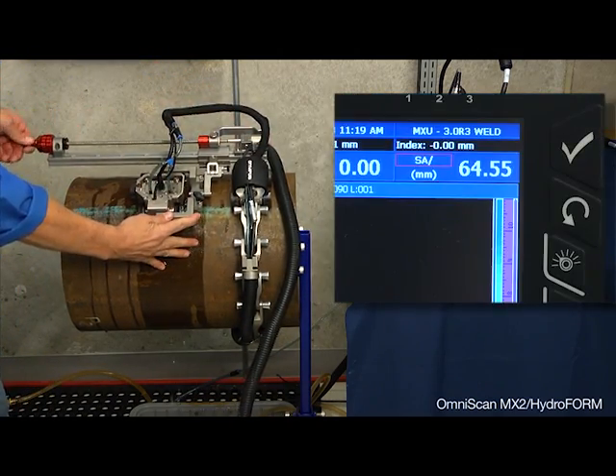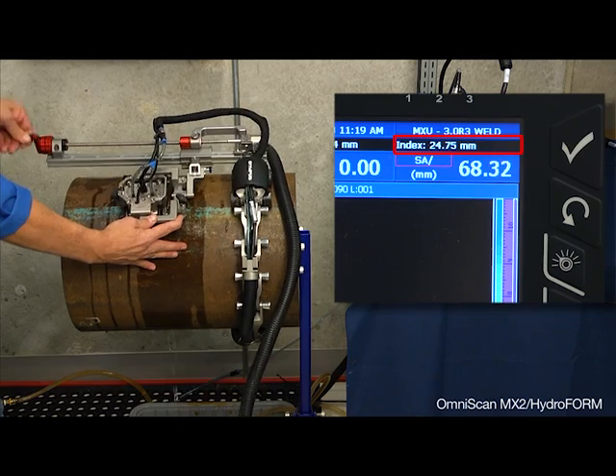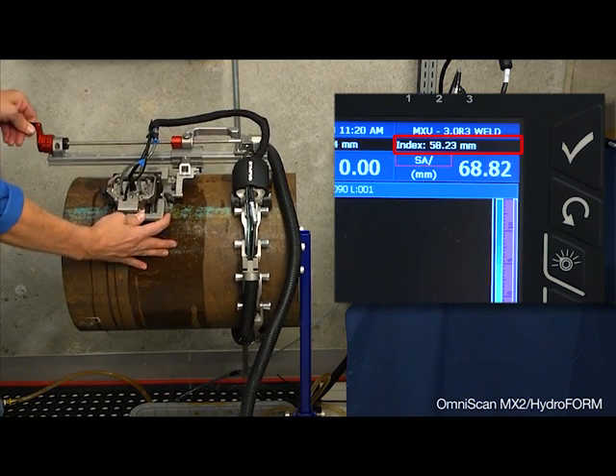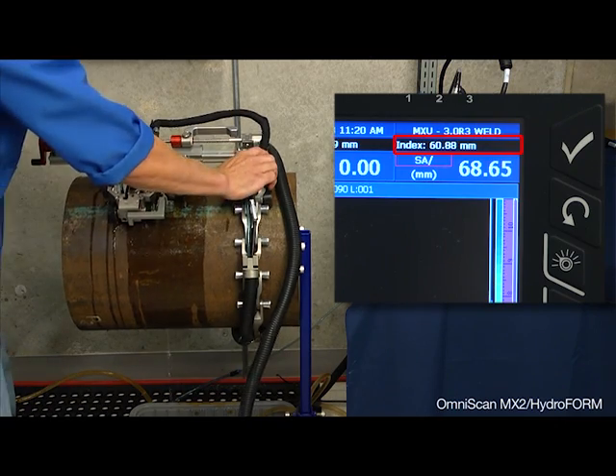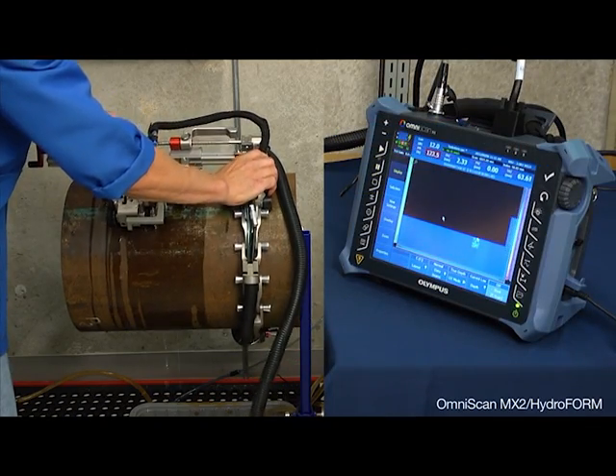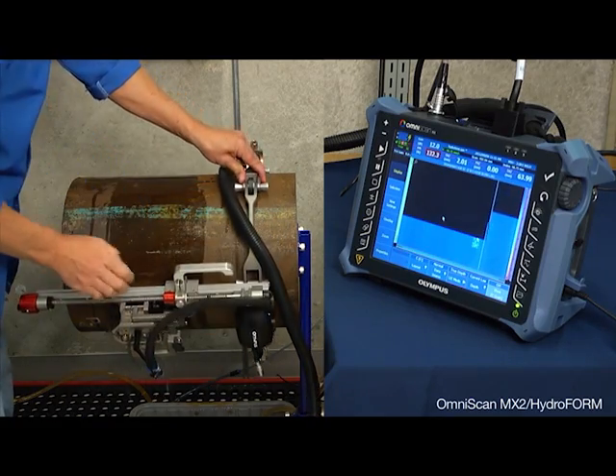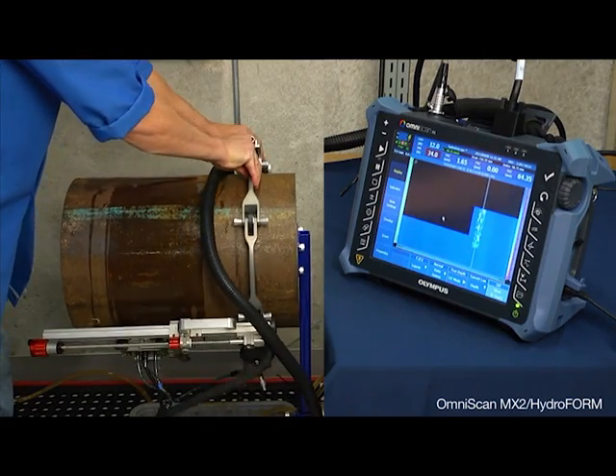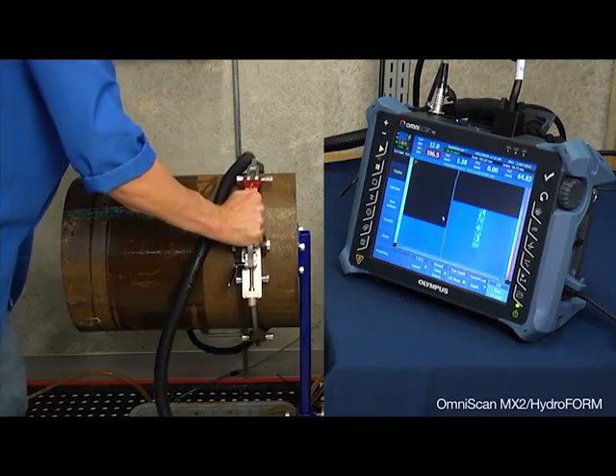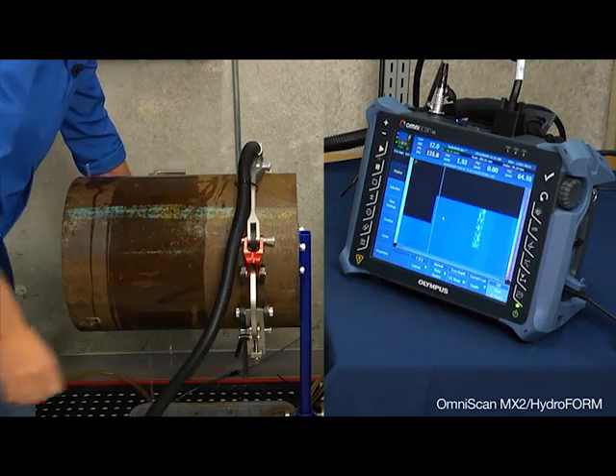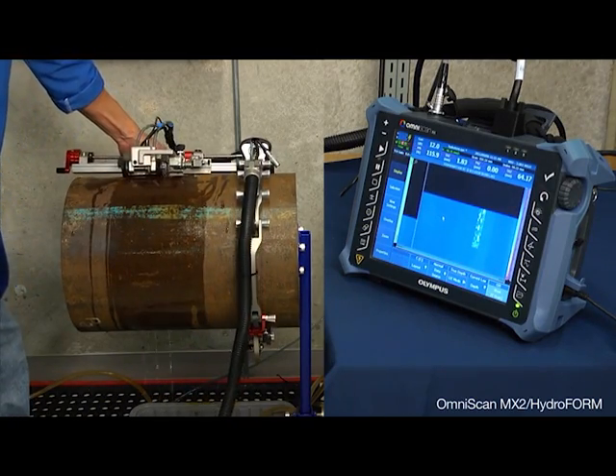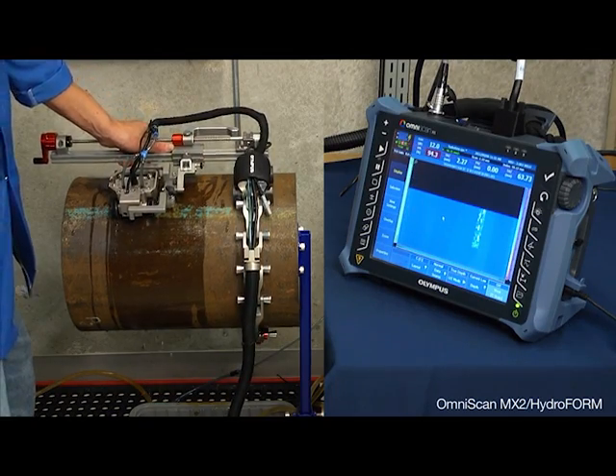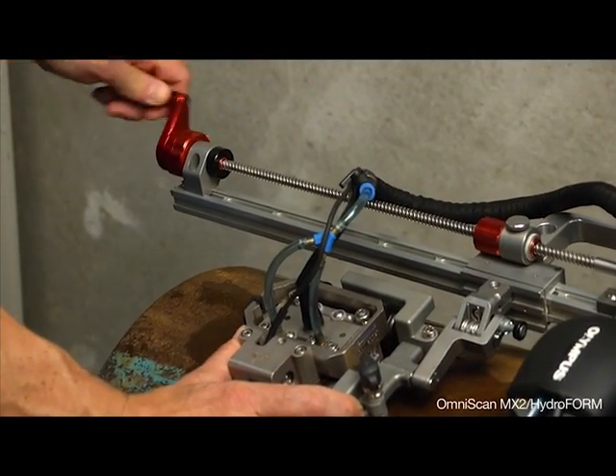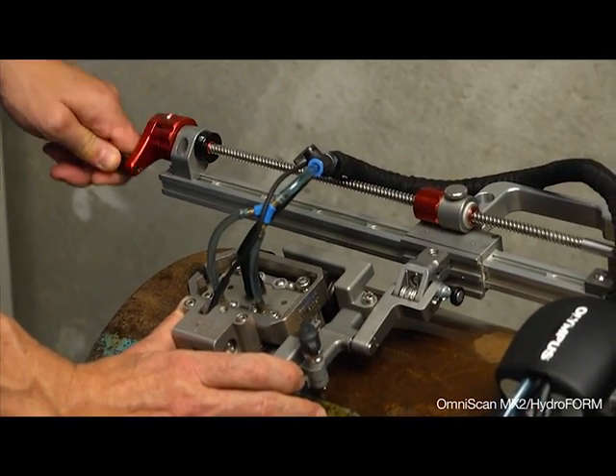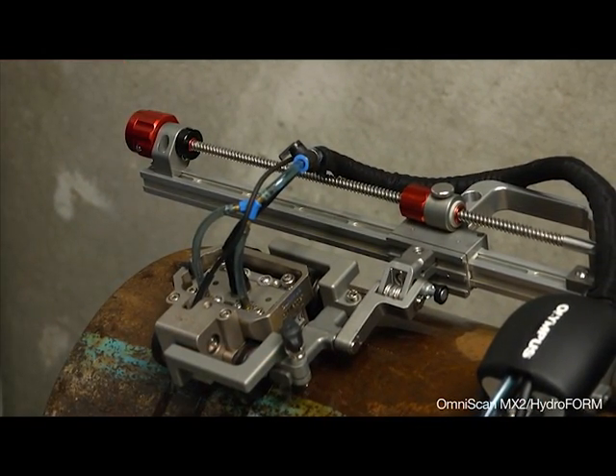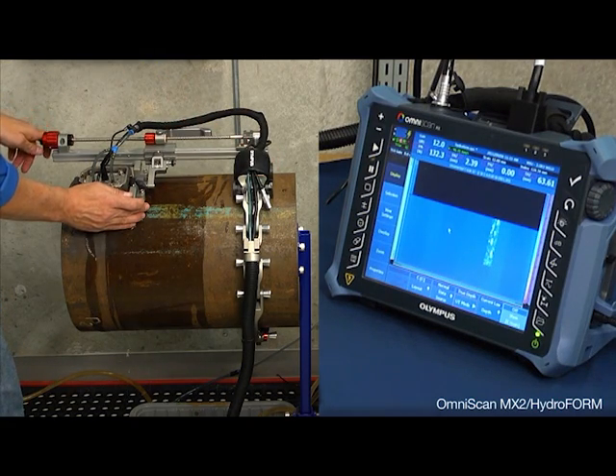While watching the index axis encoder, I'm going to scoot the scanner over on the index axis to 60 millimeters with about a 1 millimeter overlap between strokes. And begin acquiring the next acquisition. Again, while watching the index axis, I'm going to move the scanner over another 60 millimeters. Ensure that we're not missing any data. We have enough overlap.